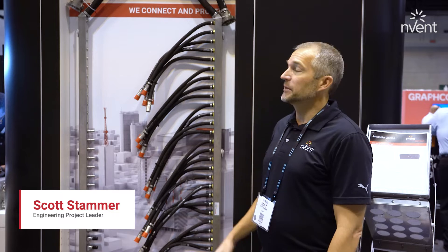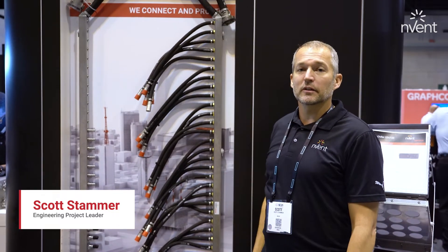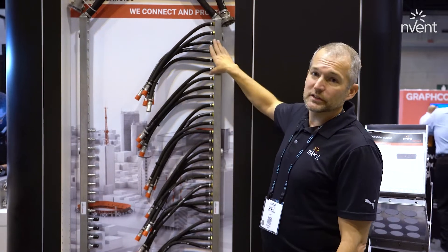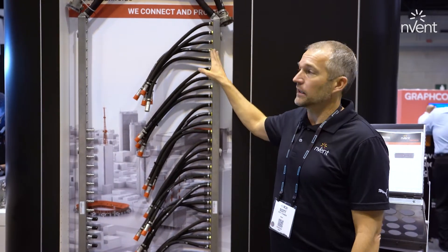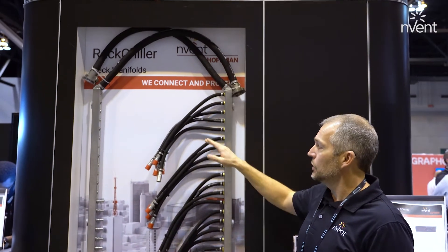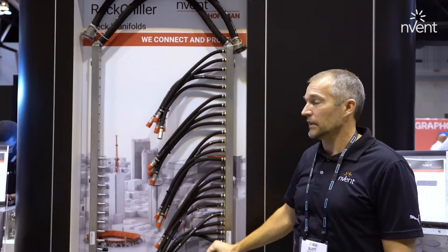This is Scott Stammer, Engineering Project Leader with nVent. I'm here today to talk about our rack chiller rack manifolds, as part of our liquid coolant portfolio. These are designed to be mounted in the IT rack and deliver coolant fluid from the CDU to each shelf within the IT rack.